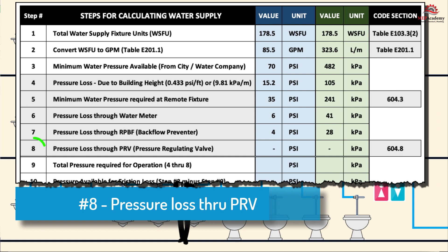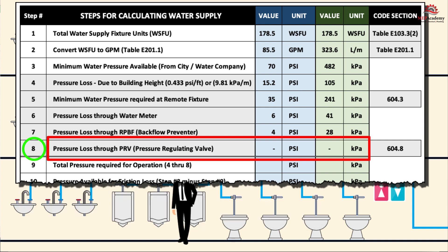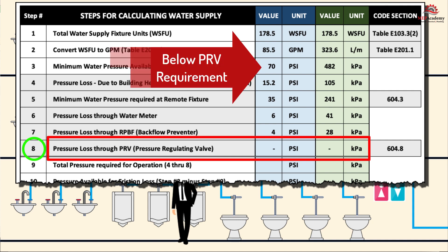Step 8: Pressure Loss Through Pressure Regulating Valve. The IPC requires a pressure regulating valve (PRV) when supply pressure exceeds 80 PSI (552 kPa), to reduce water hammer, limit excessive loss from pressure relief valves, and protect equipment and fixtures. Since the maximum water supply pressure in our example is less than 80 PSI, there is no need for a PRV.